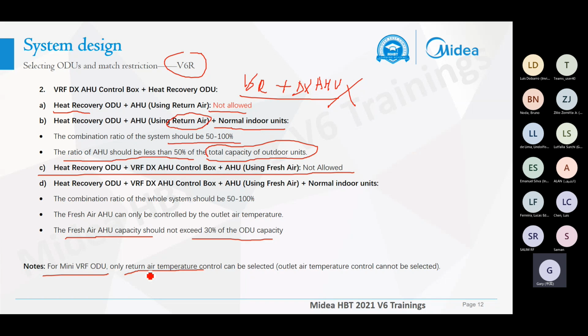Maybe you have a question: why can't we use the fresh air control mode in the mini VRF systems? The reason is that the mini VRF system is too small. Normally the fresh air has a big temperature difference from the return air. So when the fresh air comes from outside, it will cause the outdoor unit to output much more capacity. But our VRF normally has smaller capacity. So when the fresh air comes from outside, the VRF will run at over frequency. So maybe there will be some errors, and the system is not very reliable. So we don't allow you to use the mini VRF to connect to the fresh air mode of the AHU.